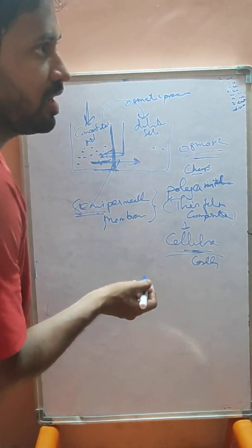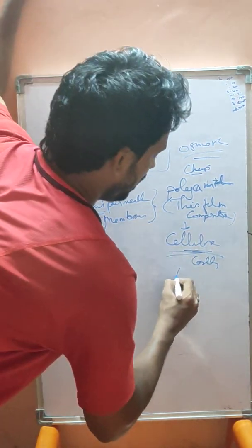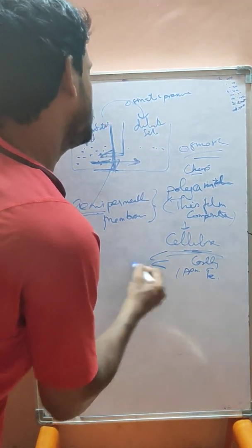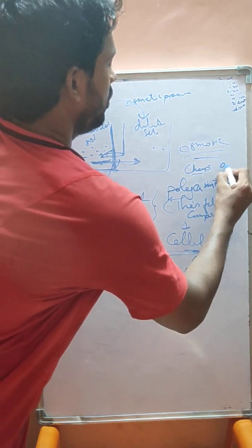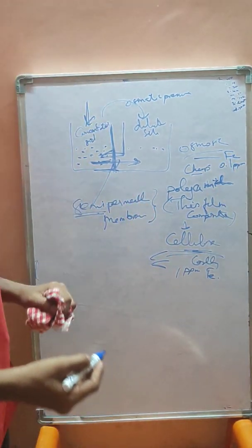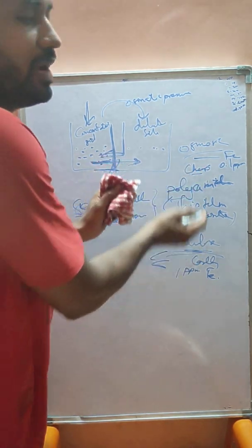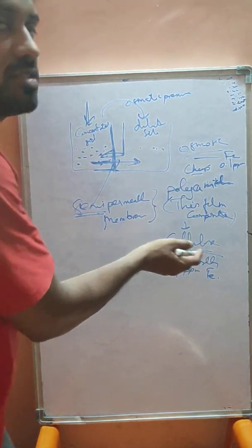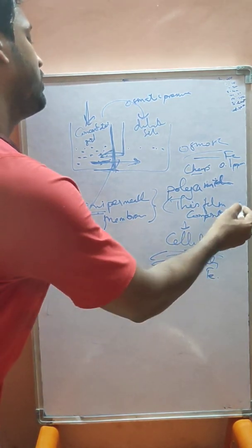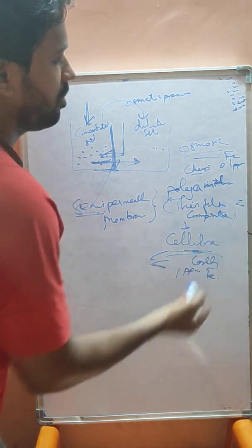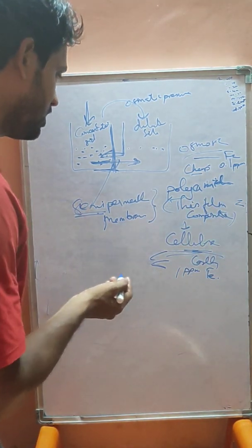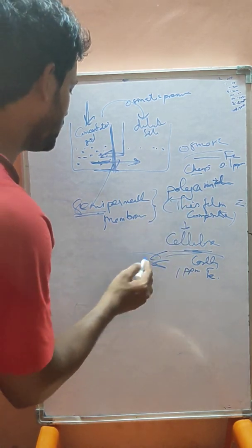Another thing is that the cellulose one will allow up to 1 ppm of iron content, but in the polyamide case it will allow only 0.1 ppm of iron content. Like this, there are many differences between polyamide and cellulose: pressure handling, maintenance and all are easier for this one, long life. You can get more data on the website. Okay, that was the discussion about the membrane.